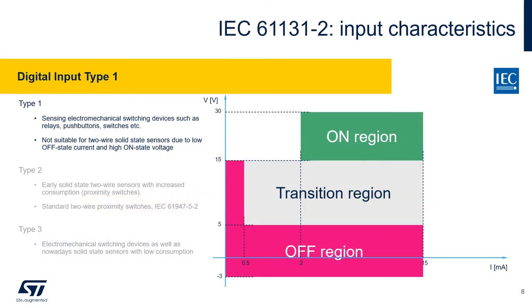The IEC 61131-2 is the key reference for input characteristics specification. There are three different digital input types specified in that norm: type 1, 2, and 3. The IEC standard specifies three operating regions for each characteristic type. They are marked as off-region, transition region, and on-region. The voltage and current limits for those region boundaries differ from one characteristic type to the other, while their shapes remain the same.